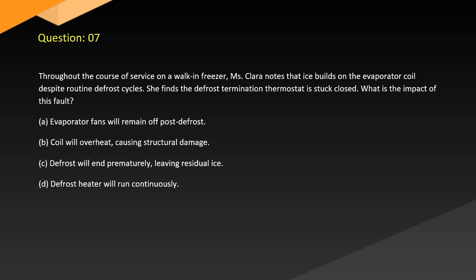Question 7. Throughout the course of service on a walk-in freezer, Clara notes that ice builds on the evaporator coil despite routine defrost cycles. She finds the defrost termination thermostat is stuck closed. What is the impact of this fault? A. Evaporator fans will remain off post-defrost. B. Coil will overheat, causing structural damage. C. Defrost will end prematurely, leaving residual ice. D. Defrost heater will run continuously.